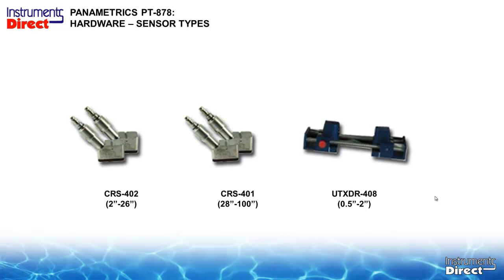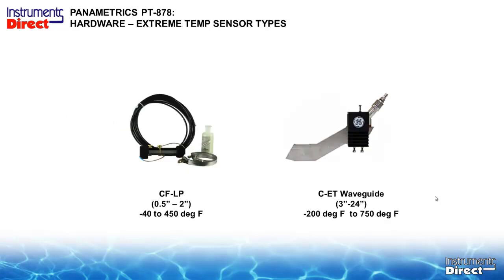And it's designed as a 4 megahertz transducer to go from about half an inch to 2-inch pipe sizes. Then we get into some of the specialty transducers, another small pipe sensor that we have for high temperature. And this guy, the CFLP series, will go up to 450 degrees. And even higher than that, well, that hockey stick to your right there, this technology has been around for a long time. It's called a waveguide, and basically it's a heat sink. And the transducer goes on the end of this heat sink, basically dissipating the heat. And you can go up to temperatures as high as 750 degrees, but it is not inexpensive.